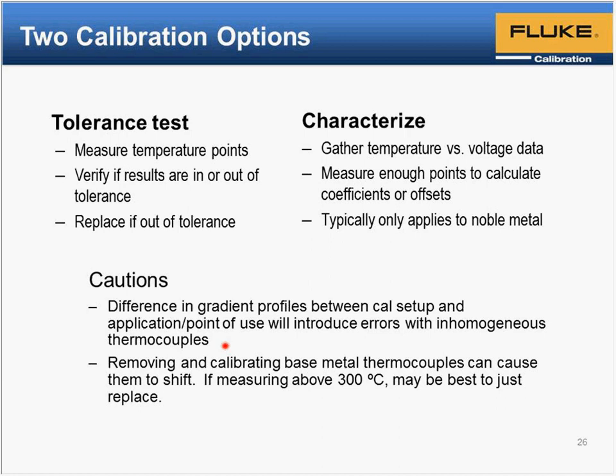Yes, with base metal thermocouples, just calibrating them may cause them to change, especially at higher temperatures. So the rule of thumb is that if you're using them above 300 degrees C, you may not be able to calibrate them. It's kind of goofy to think that calibrating it will just cause it to change, and you may not be able to capture what your customer was seeing. But below 300, they are very reproducible and there's definitely value in calibrating them.